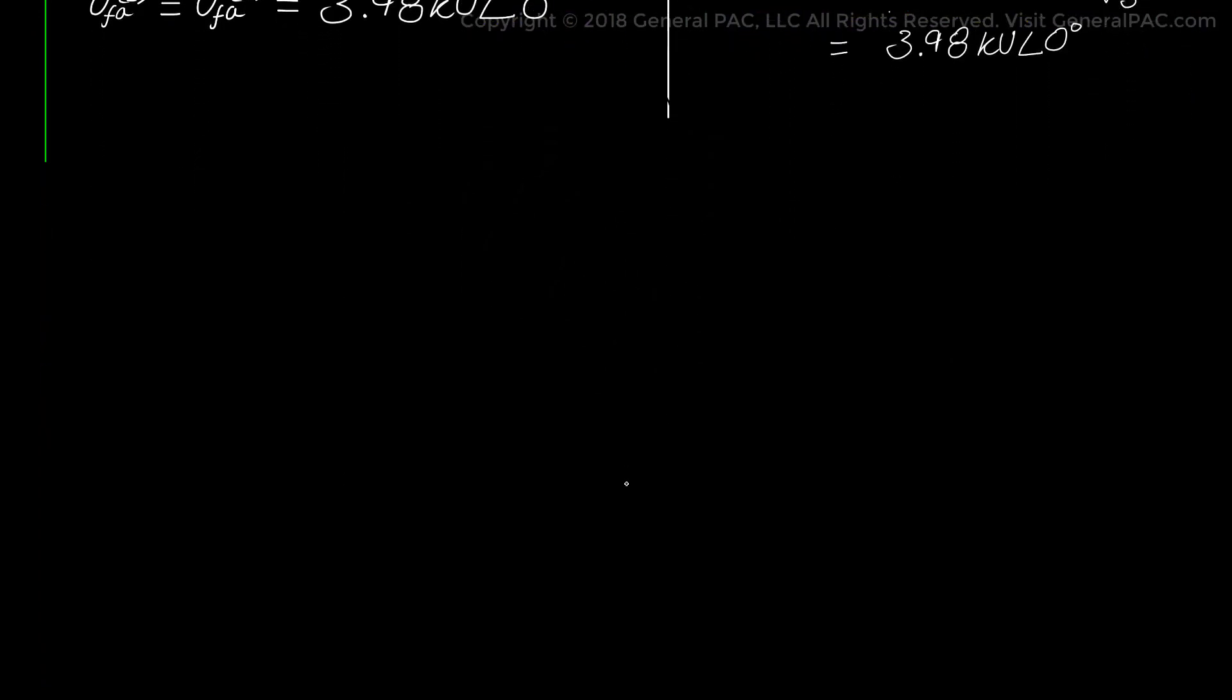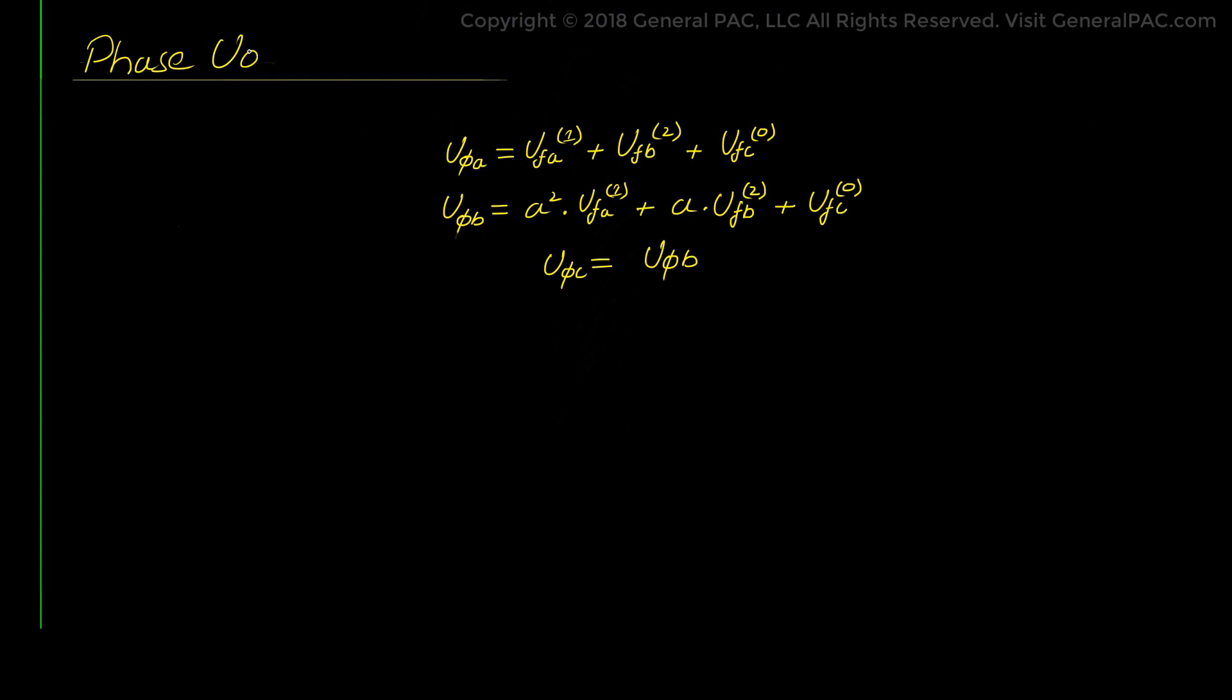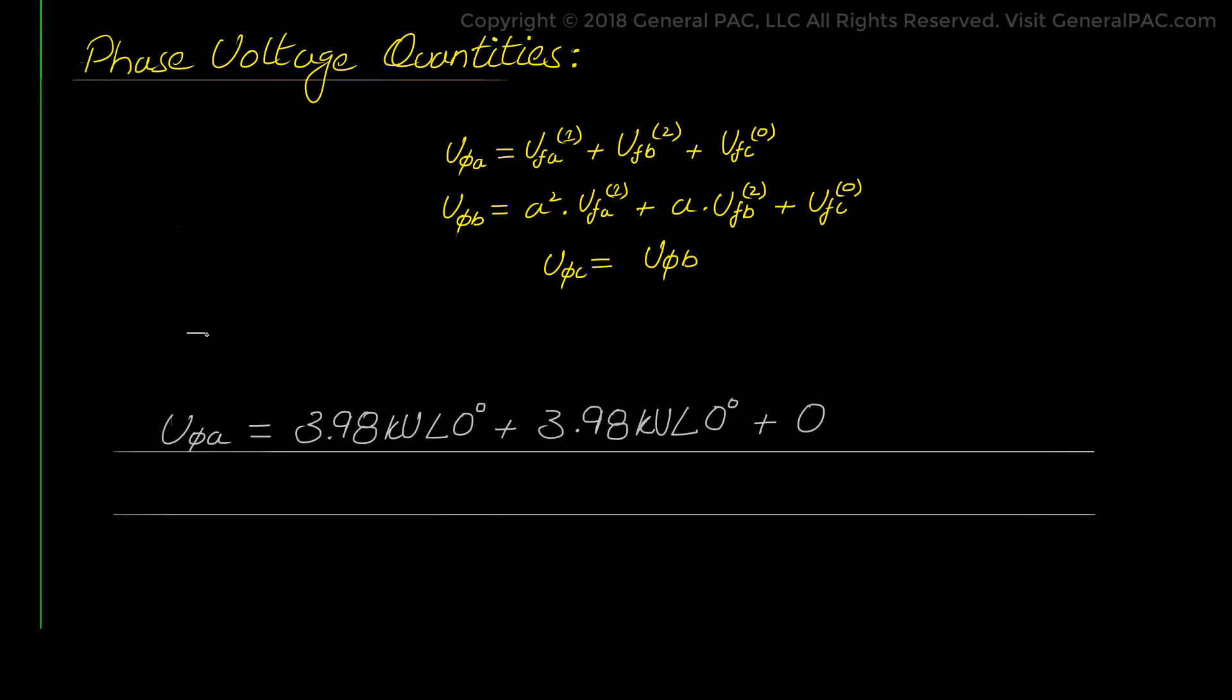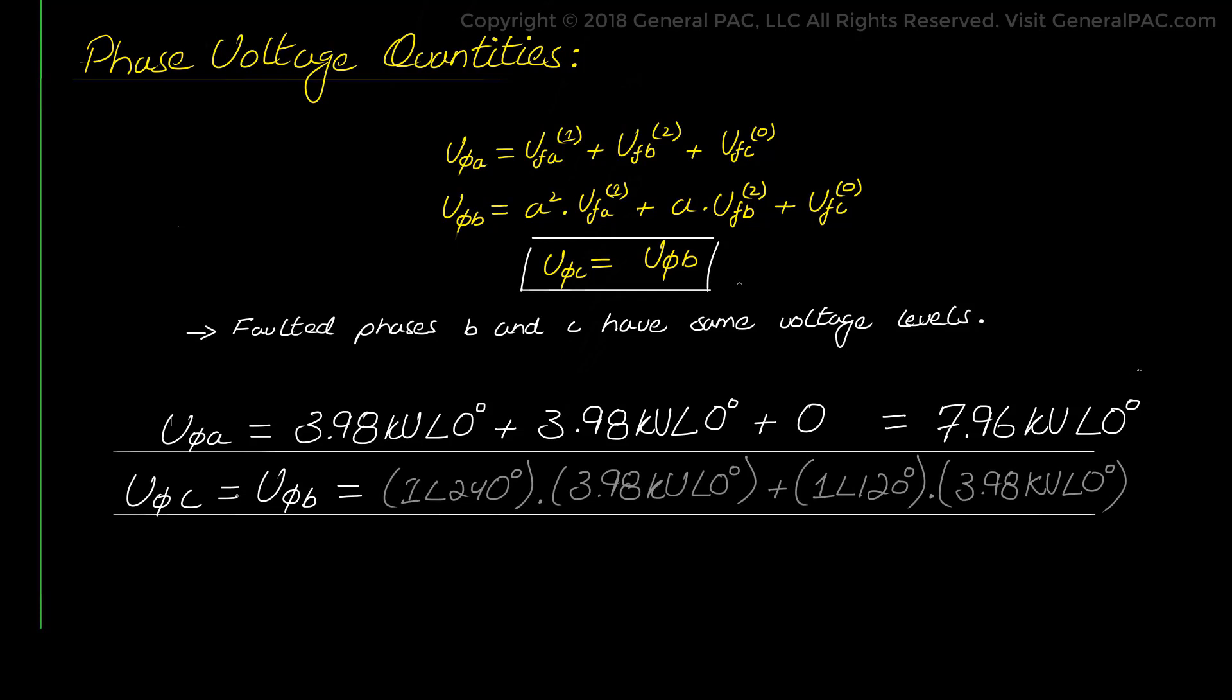Now we are left with the task of applying our familiar transformation equations to get the phase voltage values. And we do this by plugging in the calculated sequence components and the A operator, as shown below. Now we have the added advantage here because since faulted phase B and C will have the same voltage levels, V phase B equals V phase C, we will only have to calculate two phase voltages, which is V phase A and V phase B. Of which V phase A gives us 7.96 kV and VB and VC will equal 3.98 kV.